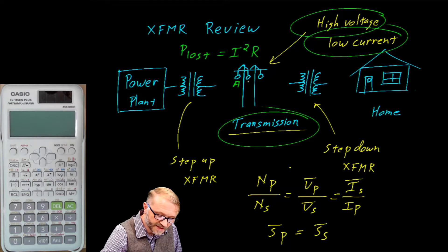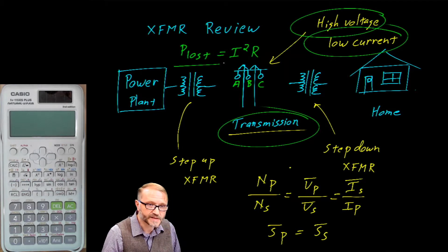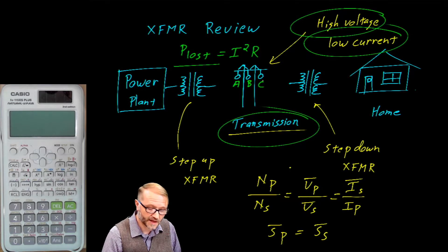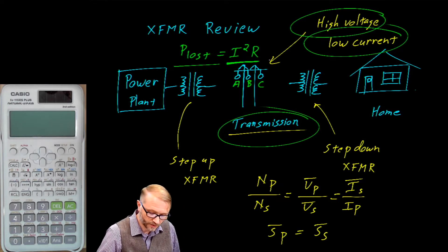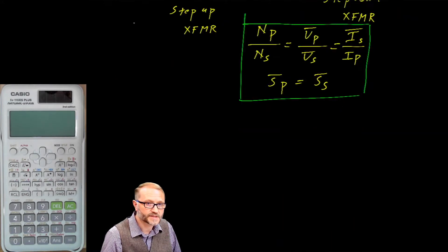Remember, we have our three phases: phase A, B, and C. The power lost in each of those wires is a function of current squared times resistance. You could lower the resistance, but that's going to be very expensive as you need thick, expensive wires — or you could lower the current. The transformer is the enabling technology that keeps the current low, and that is described in these formulas. Let's work an example to see that in action.